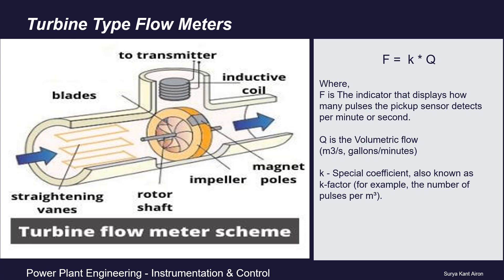The turbine flow meter equation describing the dependence between flow and pulse frequency is: f = k × Q, where f is the number of pulses the pickup sensor detects per unit time, Q is the volumetric flow in gallons or cubic meters per second, and k is the K factor — a special coefficient representing the number of pulses per cubic meter. The transmitter then analyzes the received data and converts them to analog and/or digital signals.